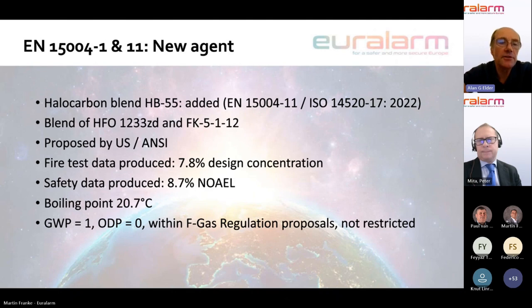So people may be aware that following this new procedure, a new agent was introduced into the standard. And for those not familiar with the way that the series works, EN 15004 Part 1 contains specific requirements that are applicable to all system technologies, and then individual agent parts address the specific properties of individual agents. The agent that was more recently introduced is known as HB55. The HB stands for halocarbon blend, and 55 describes that it's a 50-50 mix of two other components.